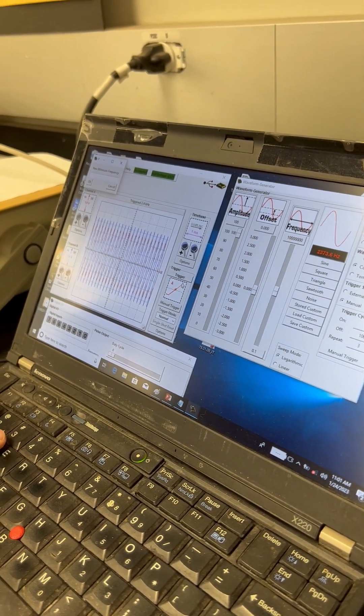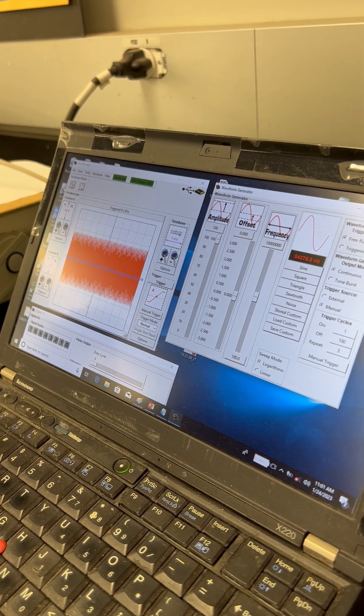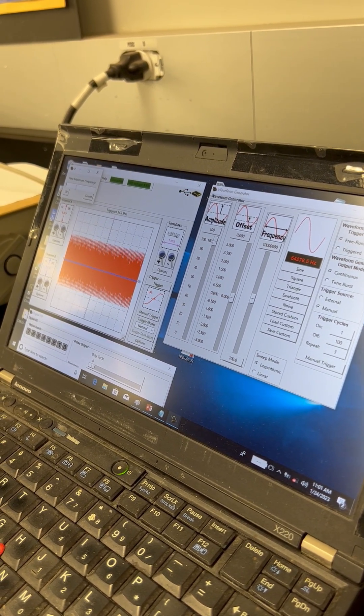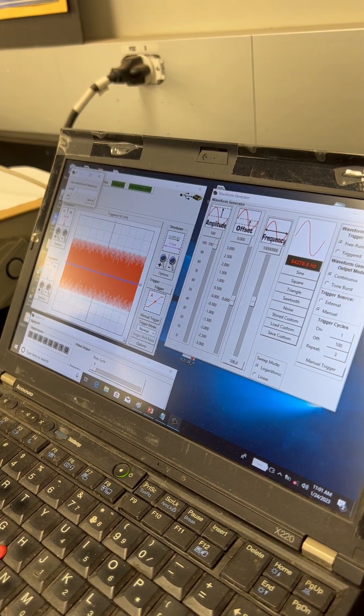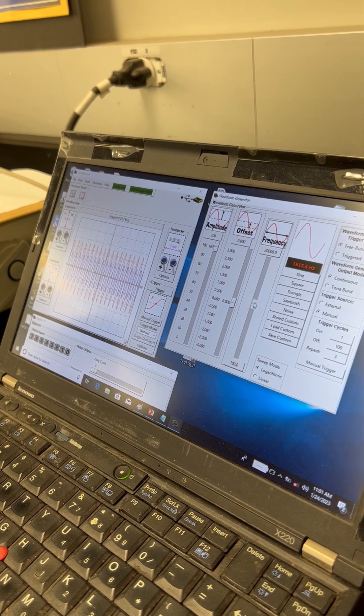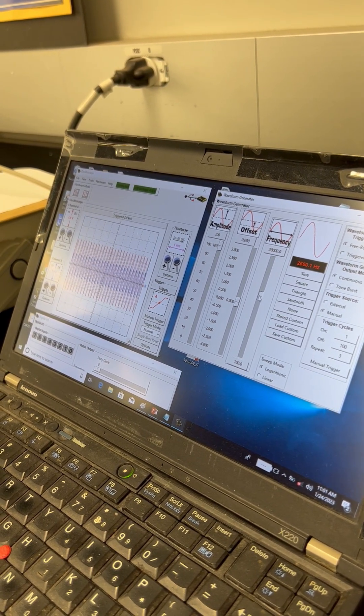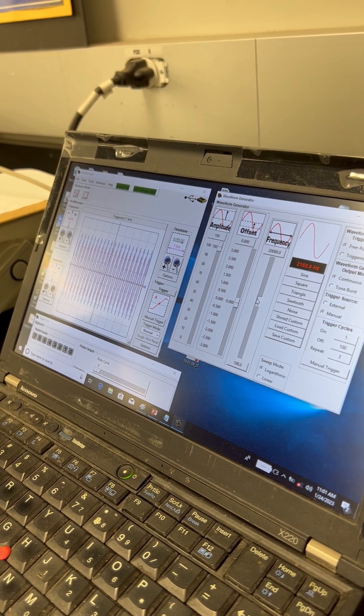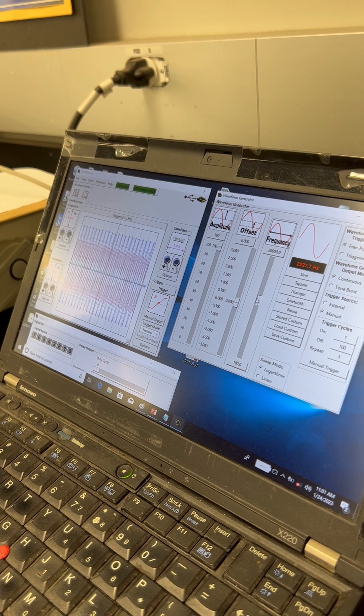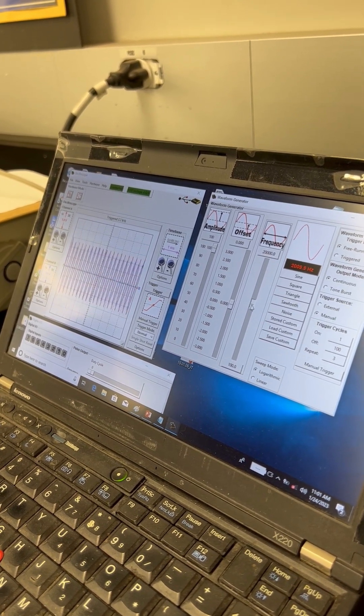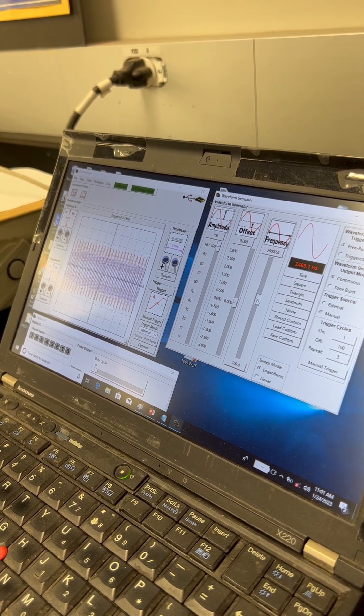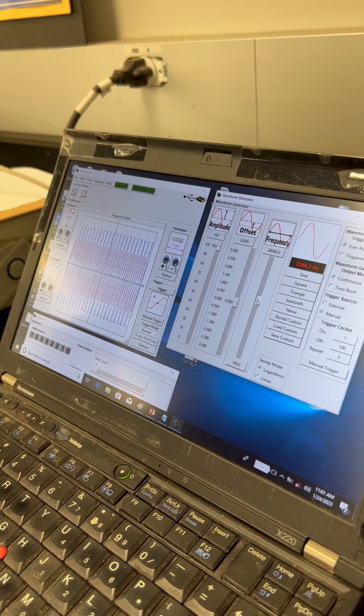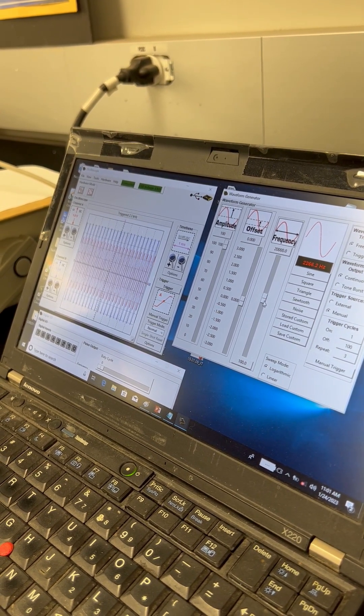So I put a hundred right there to replace the point one. And I would put 10,000 right there, 20,000 for this case to replace the very large number. So now we are working at a more narrowed range. So we can start to play with this frequency now to identify one that gives us the maximum amplitude for the receiving signal, which is about right there, maybe 2000. Yes. So I call this good.